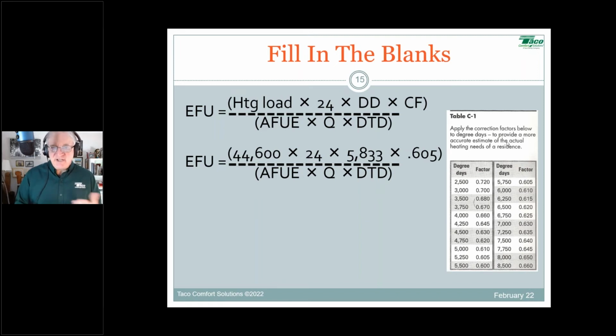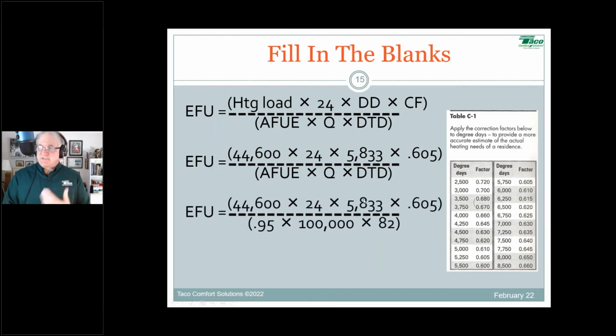So at 5,833 degree days, we could put in a correction factor, looks like about 0.605. So we've got the numerator all set. Let's fill in the blanks for the denominator: it was 95% AFUE, so 0.95, 100,000 BTUs per therm, 82 degree design temperature difference.